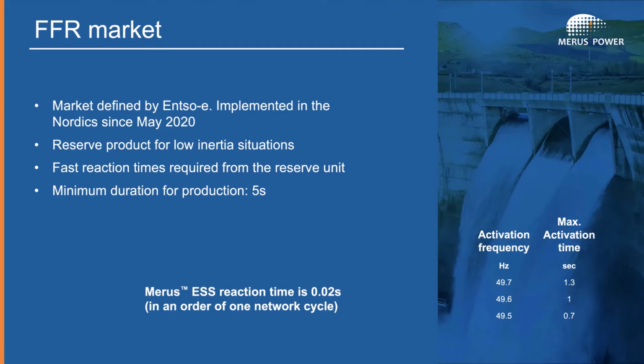Merus energy storage ESS reaction time is 20 milliseconds, meaning 0.02 seconds, so it can react very fast. It can fulfill the highest class, where the reaction time is 0.7 seconds, and the activation limit is 49.5 Hertz.